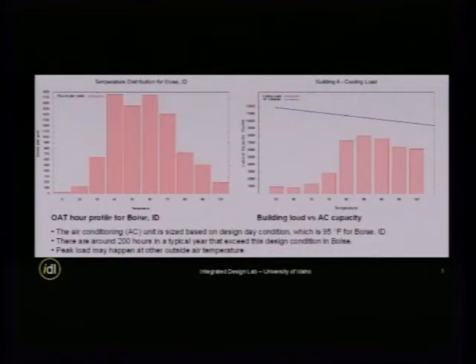So before we get to the project itself, this is how typically the sizing is conducted, and this will show you how difficult it is to do a proper sizing. If you look at the outside air temperature throughout the year, and this is the hours of the year, we can see that the predominant temperature in Boise is between 50 to 70 degrees Fahrenheit. But our design day temperature will be somewhere here, which represents probably 200 hours out of 8,760 hours.